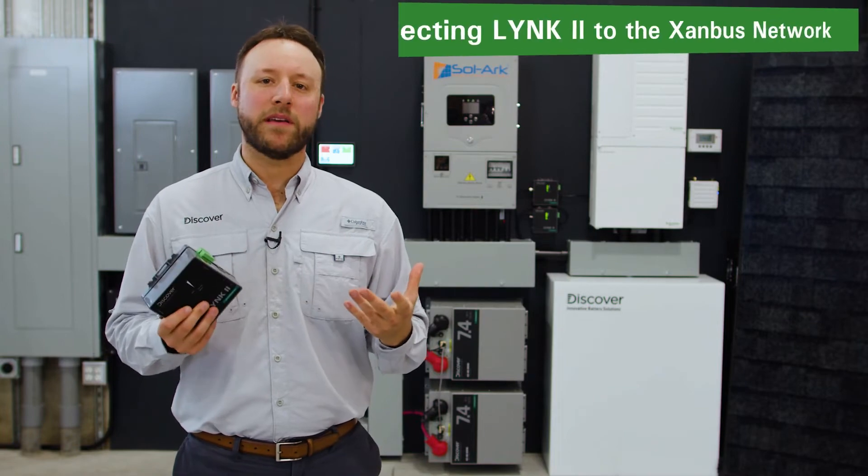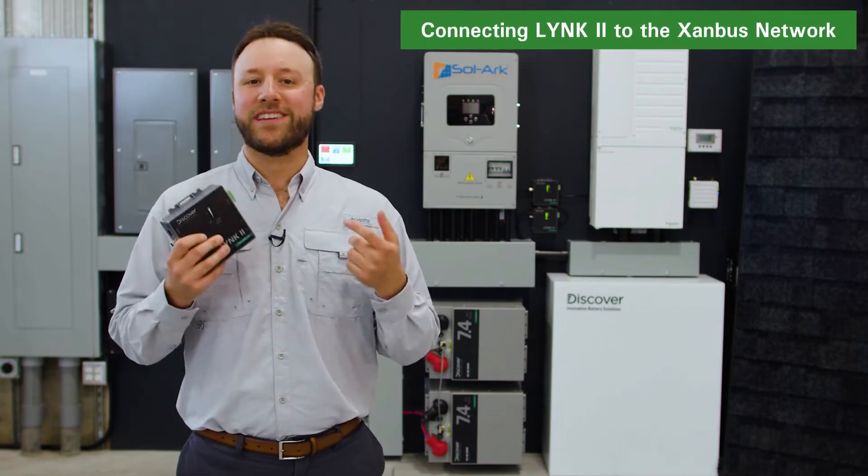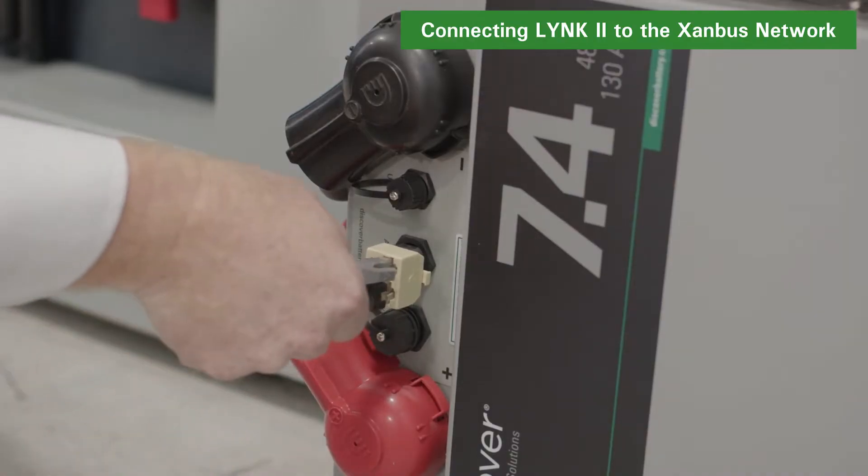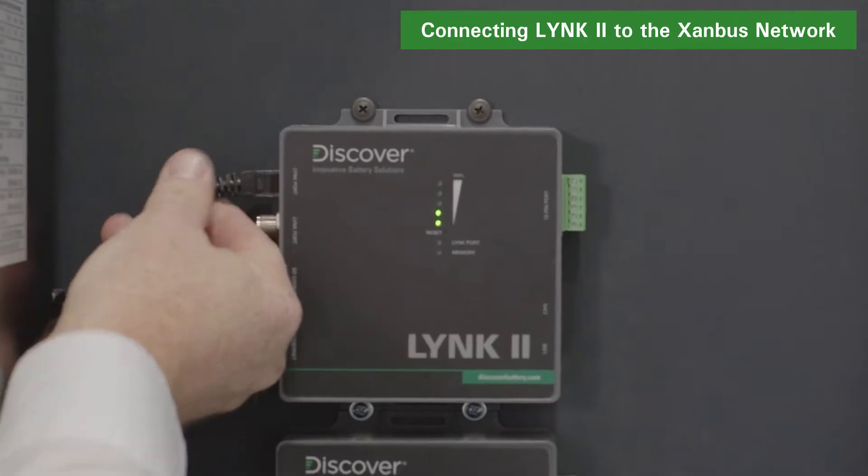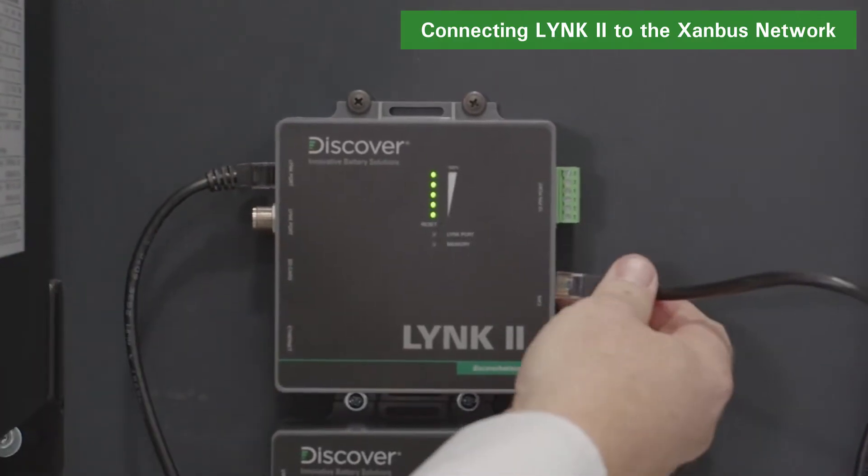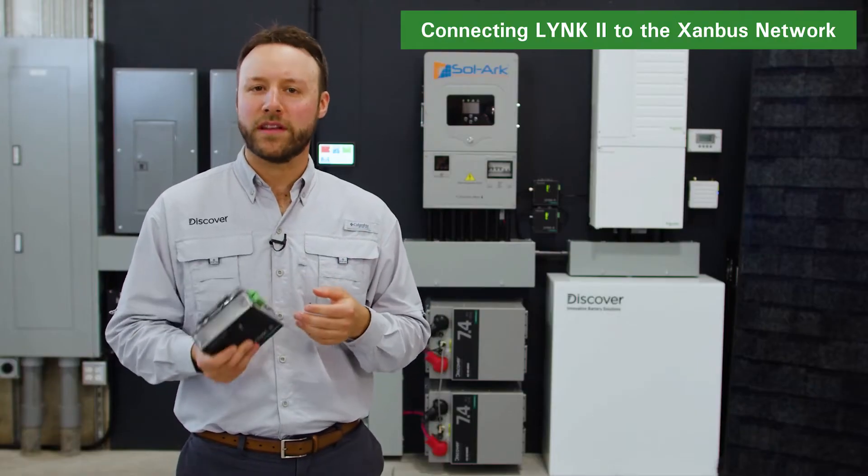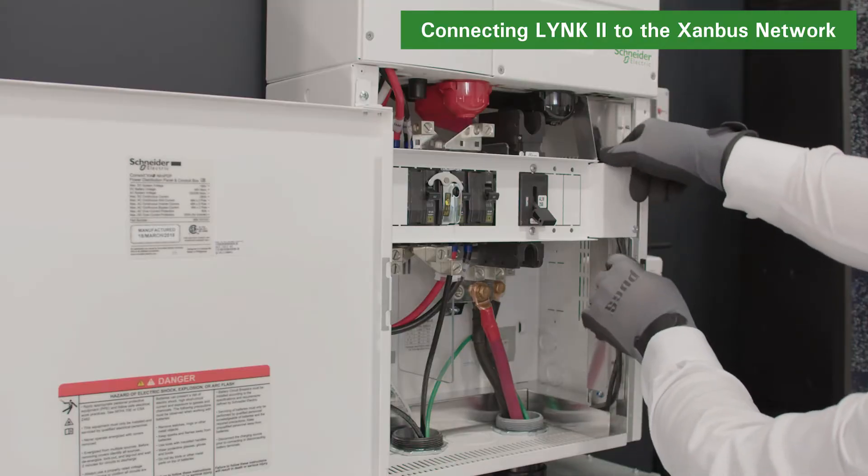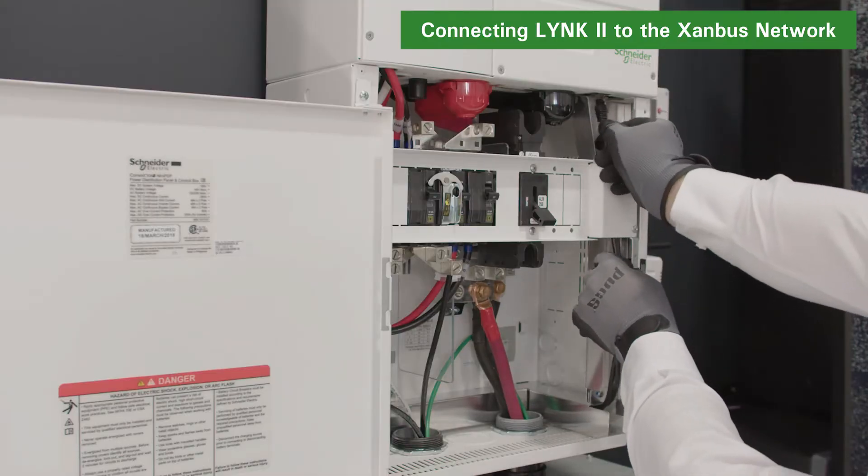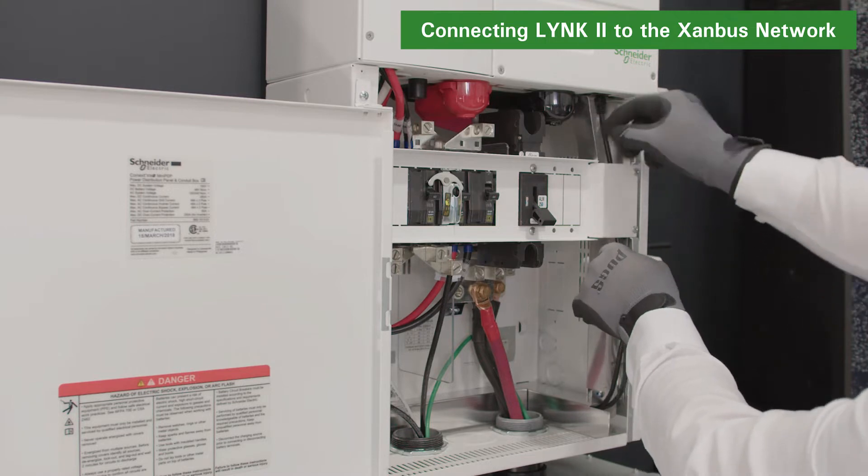Once the CAN-out pins of the LYNK II gateway are correctly configured, the Discover lithium batteries can be connected to the LYNK II using a CAT5 cable. After connecting the batteries to the LYNK II, connect the LYNK II into the Xanbus network into an open port at the end of the network.